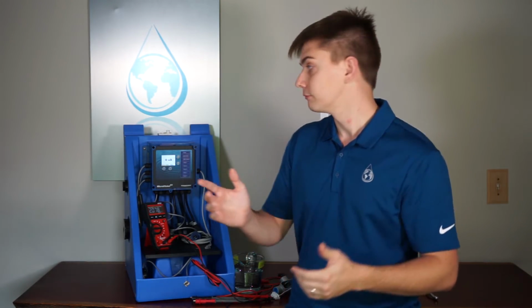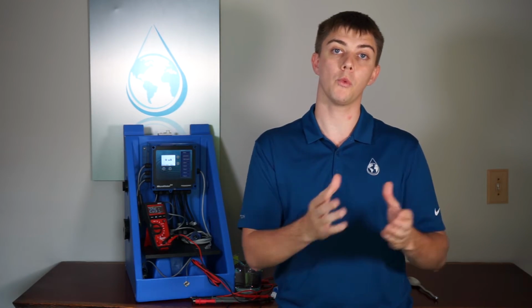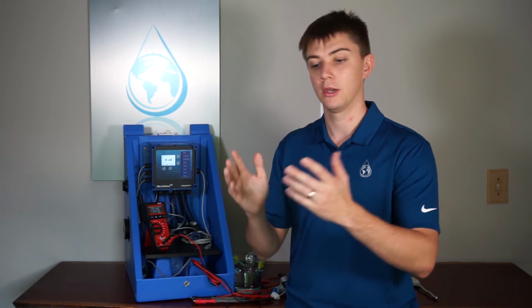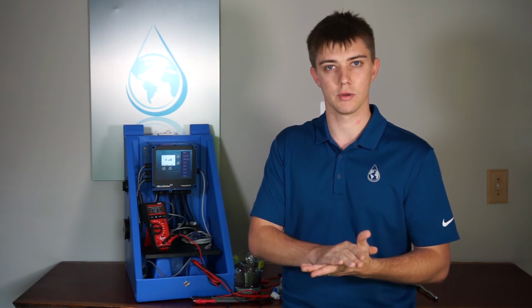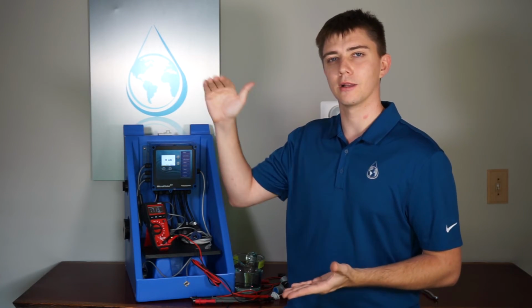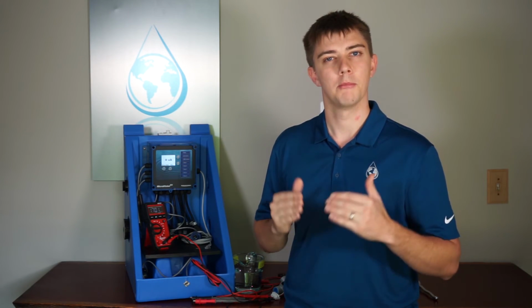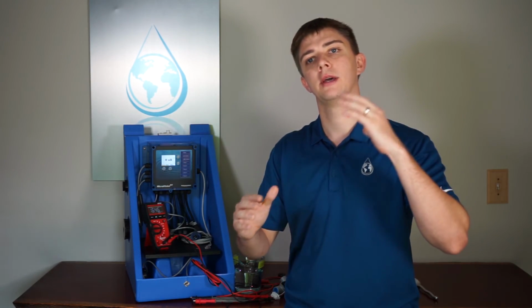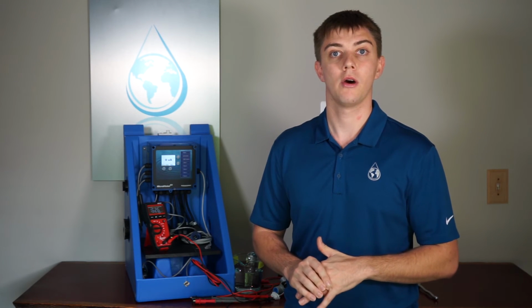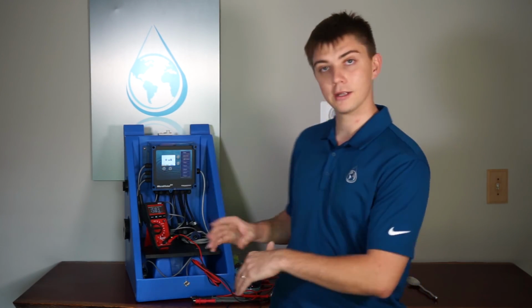Why is it important? Because you can use this to map how much you're concentrating up. You've got makeup water at a certain amount of microsiemens with a certain amount of hardness. You know what your makeup pH is. You know what your silica levels are at. So you can kind of calculate, knowing the chemistry you're using, how much could I cycle up before I'm in this gray area where it's going to cause process issues. Balancing that efficient use of water with chemical consumption, and you don't actually want to cause any harm or inefficiencies in the process by stretching that too far. So that's conductivity in a nutshell.